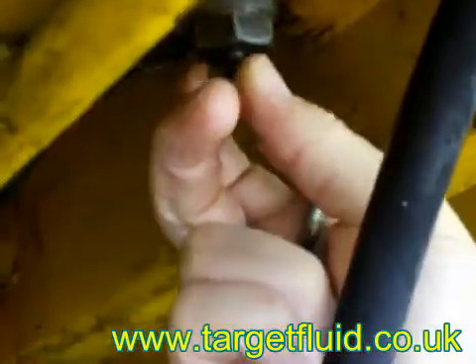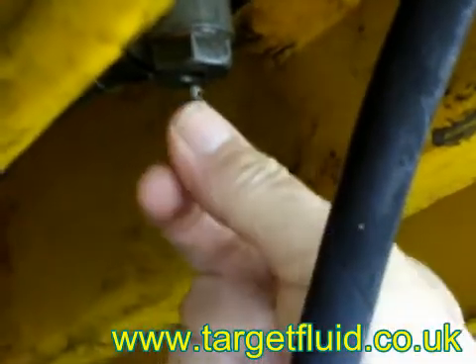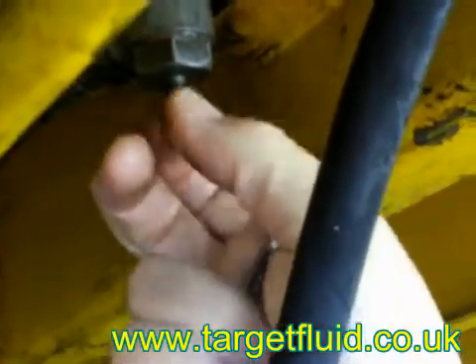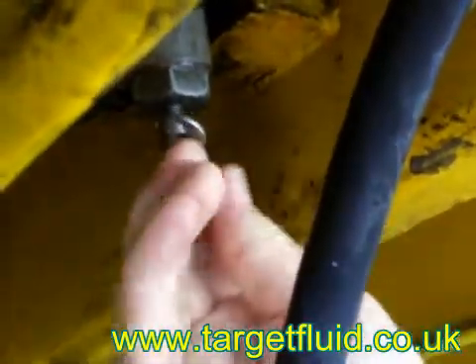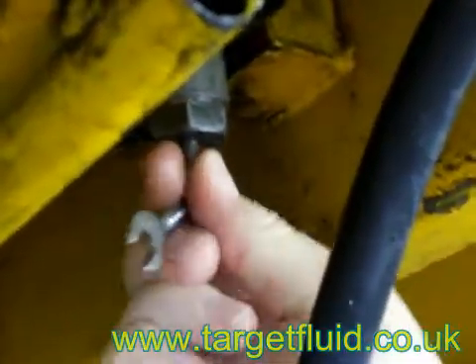When I undo these valves, you will notice that I can screw the thing completely out. That can be dangerous, especially if you've got air behind it under pressure. These could project out, and if you're in the way, cause some serious injury. So always be careful handling bleeds.